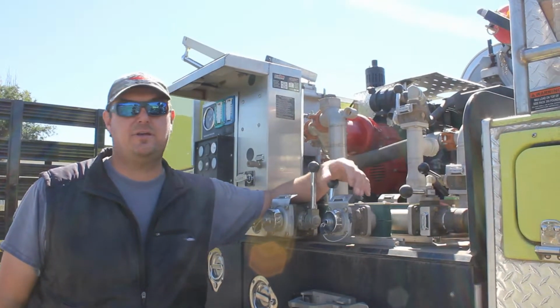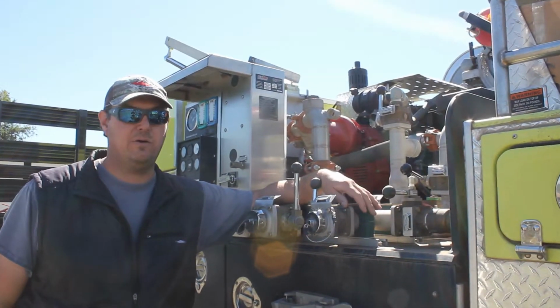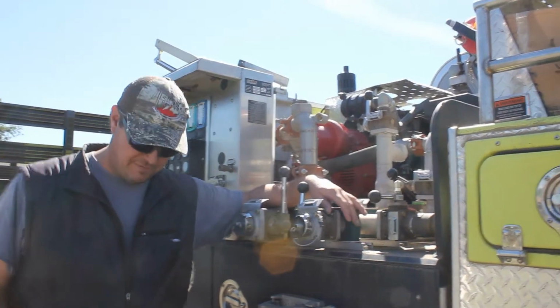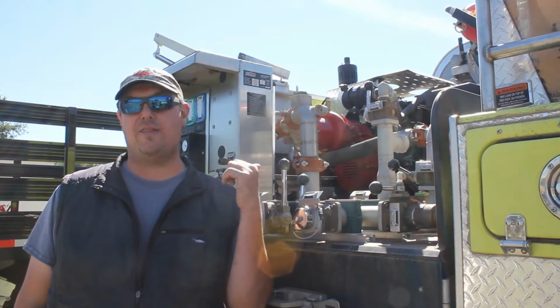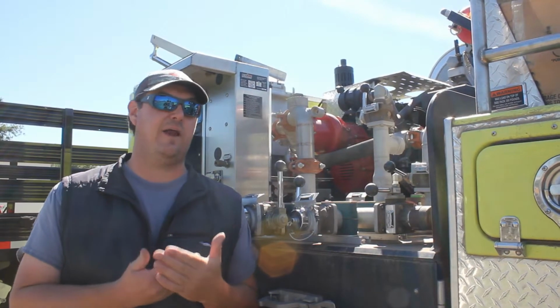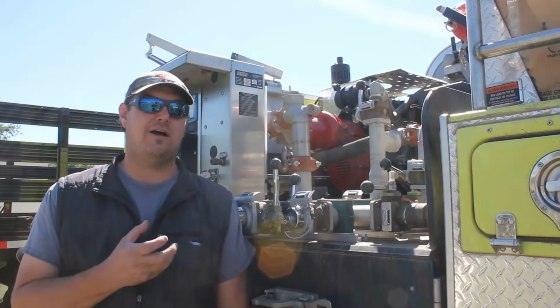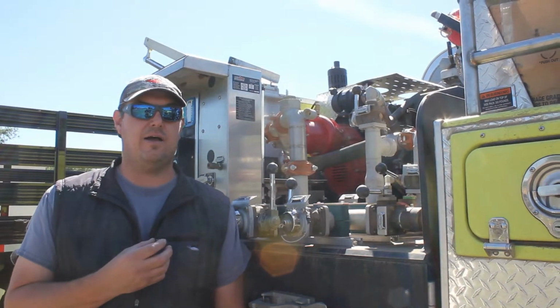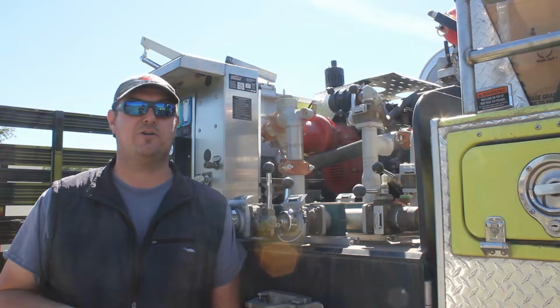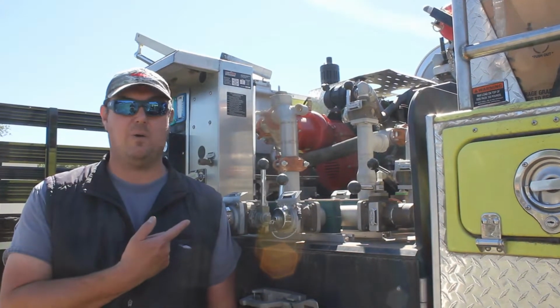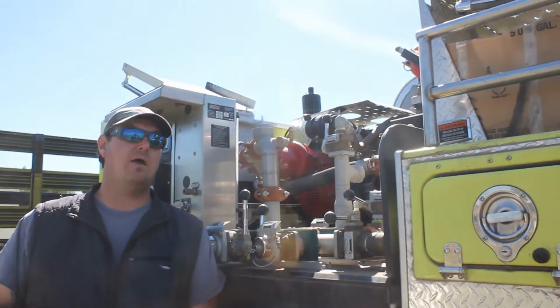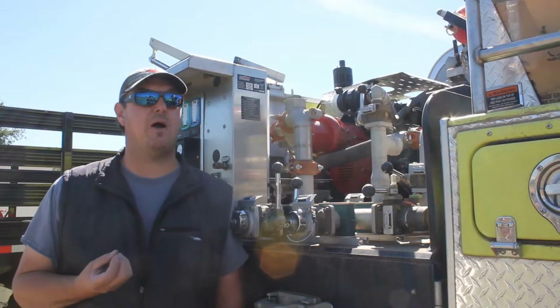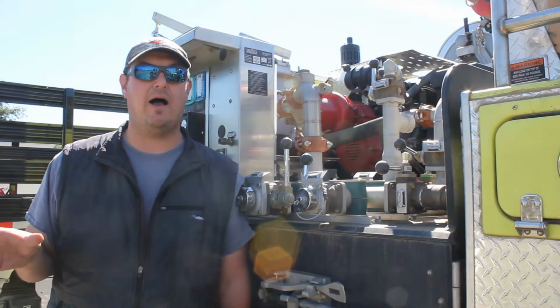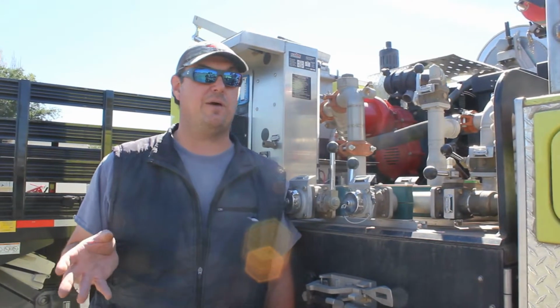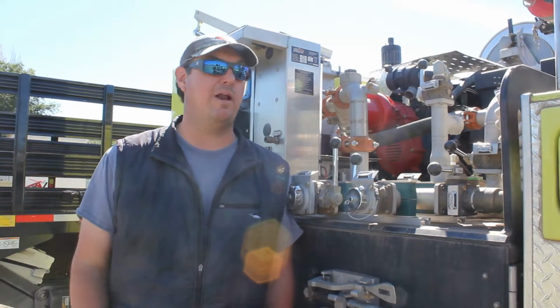The problem is this pump went down a week ago or so. It was leaking water from, I'll show you where it was leaking water from in a minute. It was leaking water at the coupler, which meant that the seal went out. The seals, I guess, are made out of graphite, not ceramic like the Darleys. Those are ceramic, they're a little bit more durable, maybe. In general, these don't go out all the time, but it went out. We don't know why. Commonly, pump seals go out from operator error. That's the main cause. Talking to the operators, I actually don't know that was the problem. Something happened, and whatever, not a big deal.